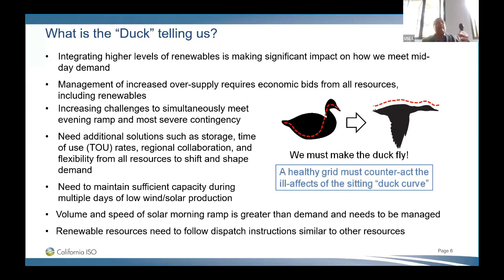Controllability is key. My last point is that there are three things you want to ask rooftop PV to provide now: voltage control, frequency control, and the ability to curtail, because we have no controllability otherwise. In California we imposed what's called Rule 21, which you can look up online. It means that if system frequency is high—because rooftop PV impacts grid frequency similar to other inverter-based resources—new rooftop PV installations automatically need to back off. If system voltage is high, they also automatically back off to help operators control the grid.